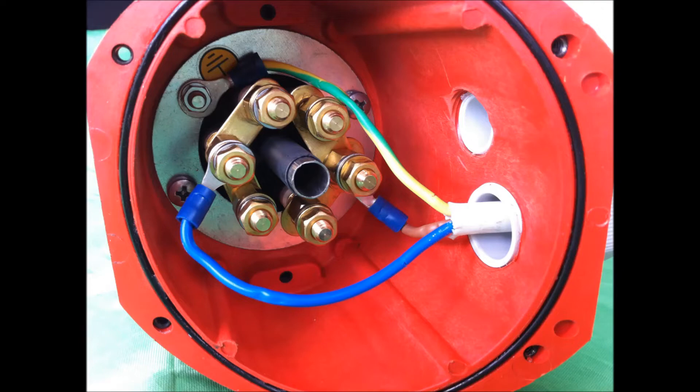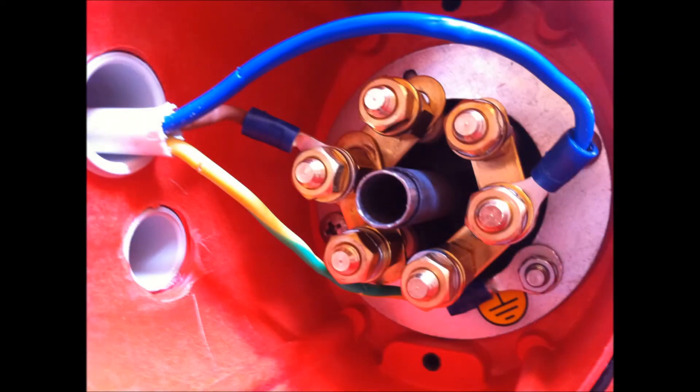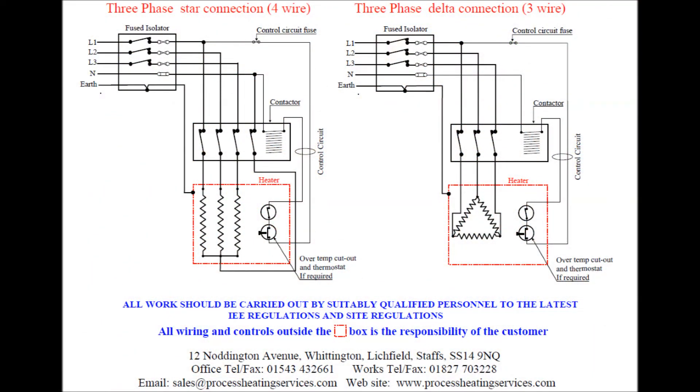Similarly, a three element immersion heater is bus-barred up to give a common live and a common neutral at either end of the three elements. All three phase immersion heaters must be connected via a contactor.